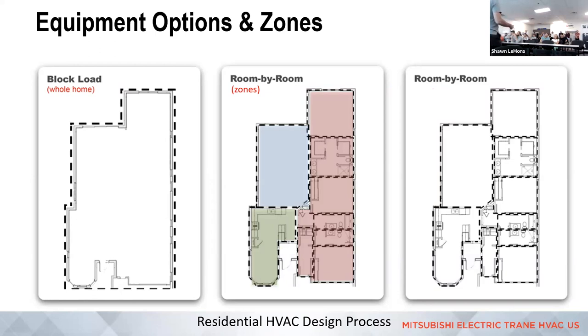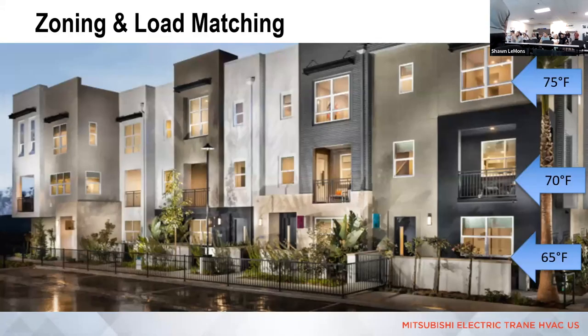If it's an older house with higher loads, we might be able to do lots of independent ceiling cassettes or wall cassettes or what have you. But in higher performance buildings, as those loads drop, you're going to run into some challenges with sizing, because while the systems are variable, they're not infinitely variable. There are some limitations. Really we're thinking about one room versus another, one floor versus another, and how we address how we live and what the exposures are.